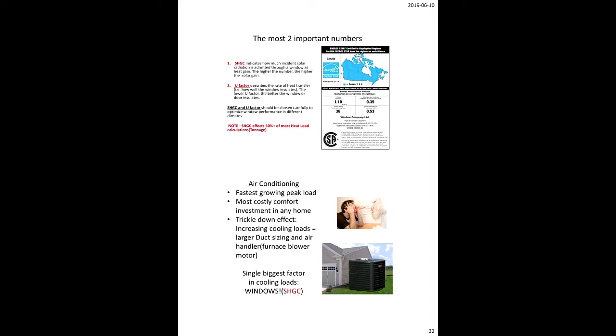We do mechanical design for some houses. We review mechanical design, and we're finding that production track builders have gone from designing ductwork for heating loads, because the home's heating loads are going down, to now designing ductwork for cooling loads, because the cooling loads are going up. So now we have to put in ductwork that changes sizes depending on the season. Have you seen that? We haven't either. And we have comfort issues. We can't maintain static in the line at certain times of the year. It's really weird. Anyways, so it's the biggest deal.